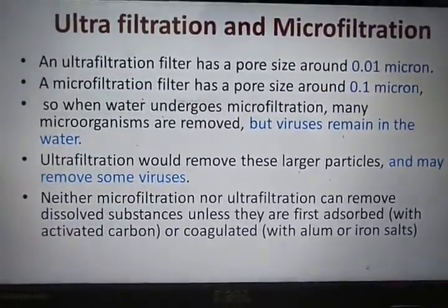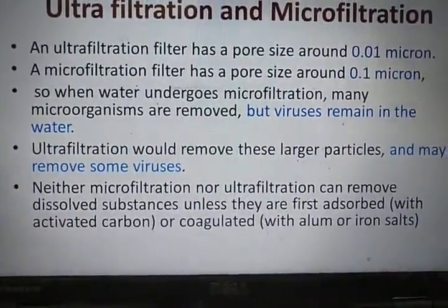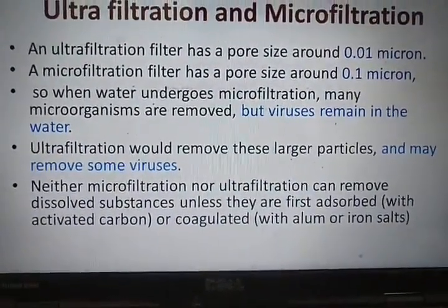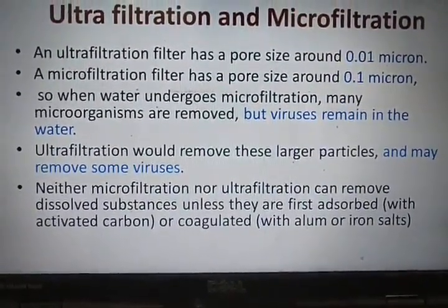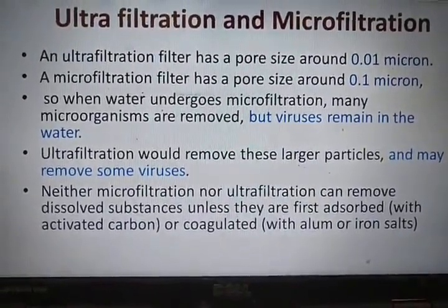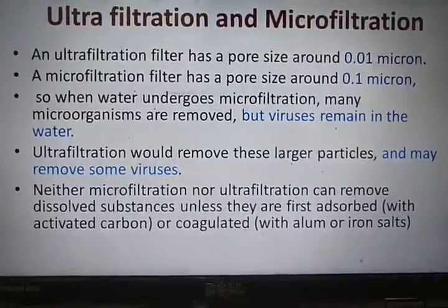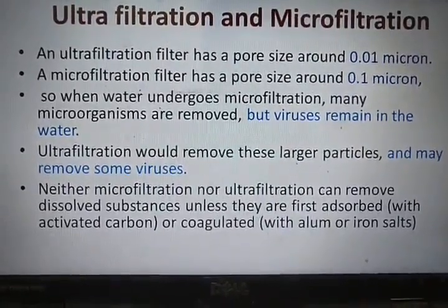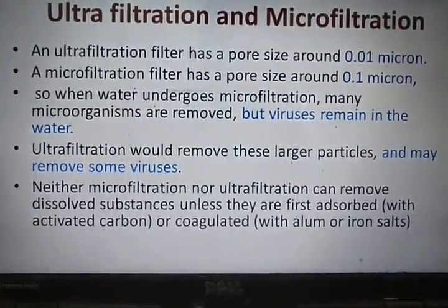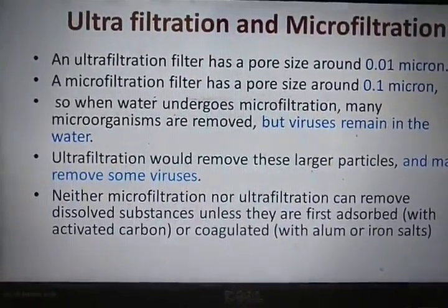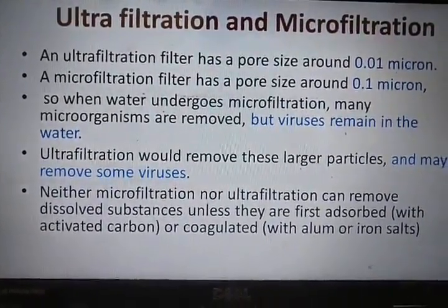Okay, when the water undergoes microfiltration, many microorganisms are removed, but some of the viruses remain in the water. Like I have shown you in the previous slide, viruses will be retained in the permeate. It is not able to remove the viruses because viruses are very small in size, so they can easily pass through these microfiltration membranes.